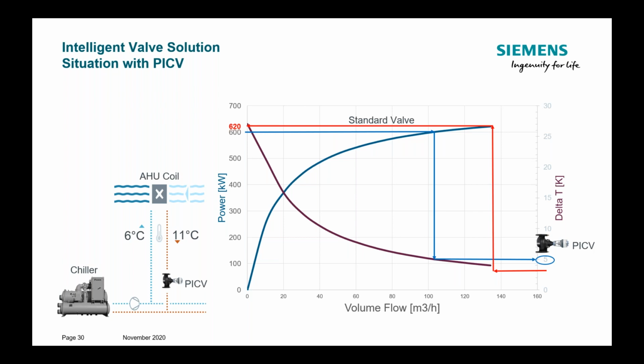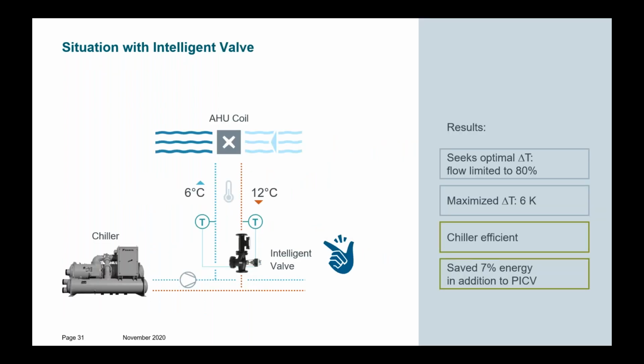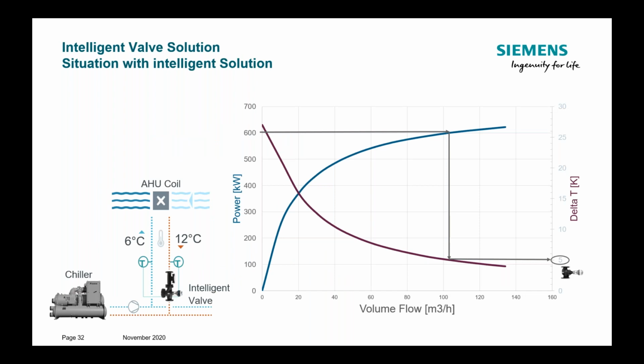Now, this is the point where the intelligent valve solutions kick in. They are able to measure the DeltaT and not only limit the flow. And if we say for this coil the real design DeltaT should be 6K, then we end up here. The intelligent valve will now measure this flow and return temperature, see that the DeltaT is violated, and decrease the flow even a little bit more than the traditional presetted PICV.